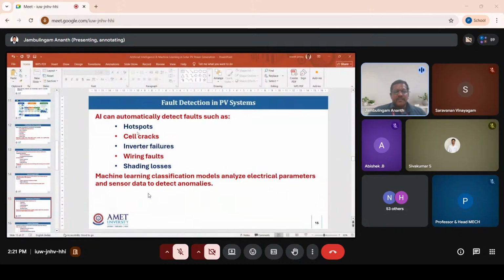When there is a malfunction in the PV modules, there will be a hotspot, and if the hotspots are not identified properly, they will lead to malfunction of the entire panel. Then cell cracks are another problem inside the solar panel modules, because of various environmental factors. Hotspots also ultimately lead to cell cracks. Then there is inverter failure. Inverter failures may be due to inefficient air supply. An inverter is a device which converts DC current into AC current. When there is no proper ventilation, it will overheat, and finally this leads to inverter failure.